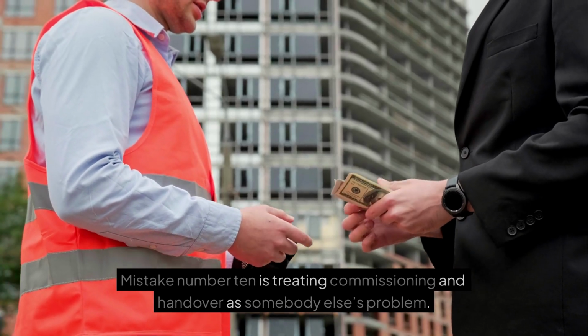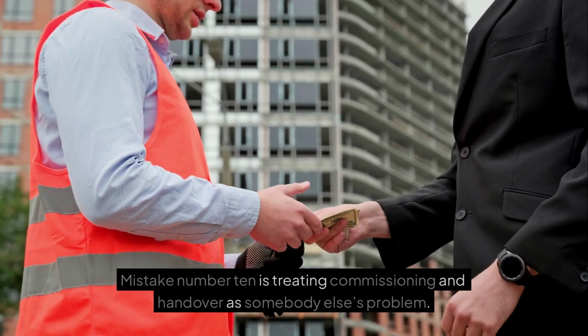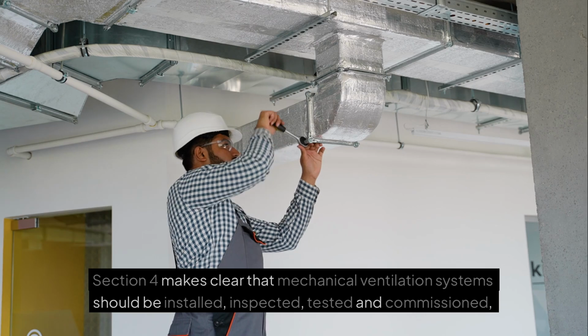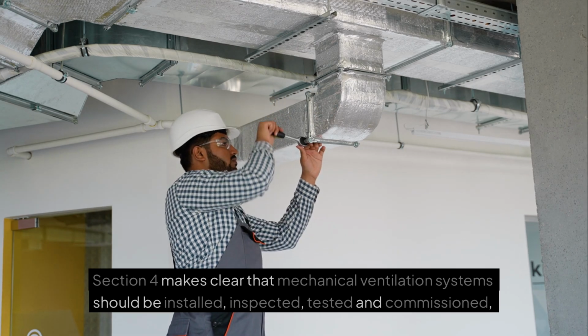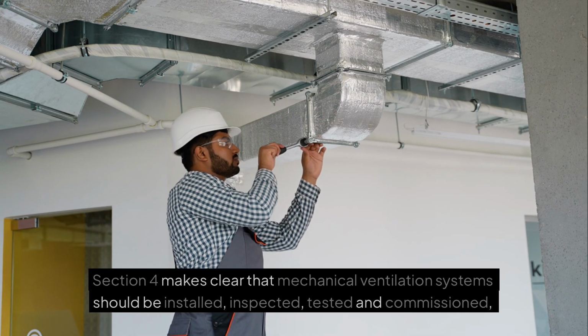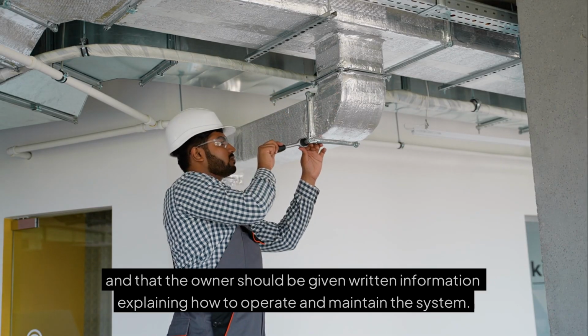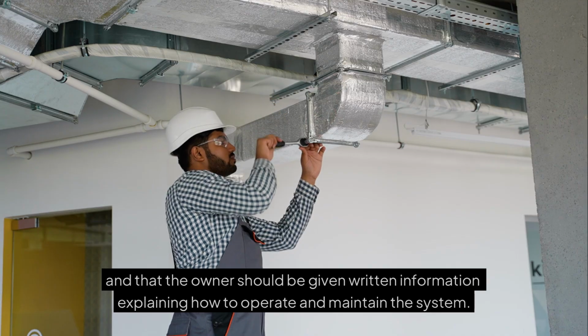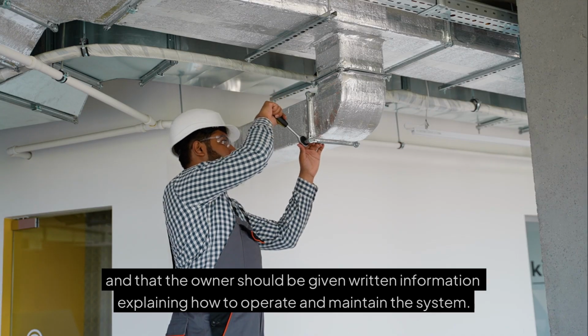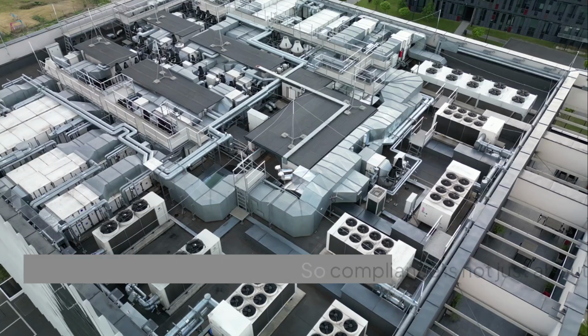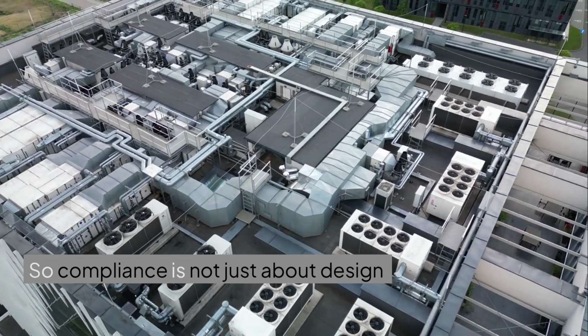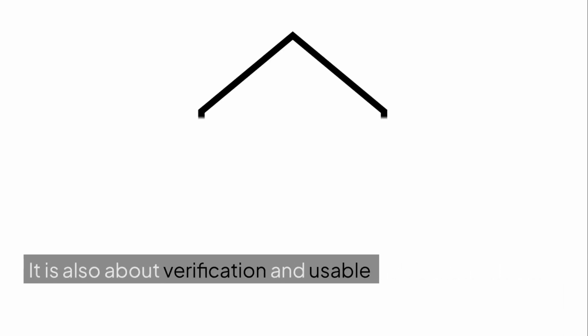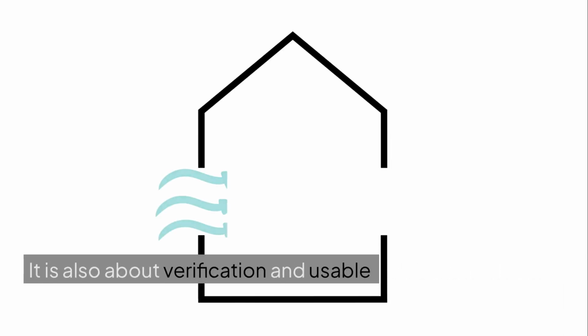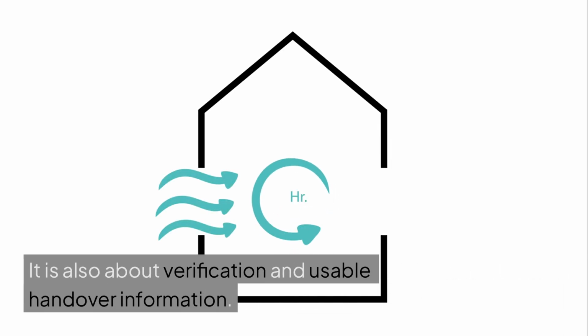Mistake number 10 is treating commissioning and handover as somebody else's problem. Section 4 makes clear that mechanical ventilation systems should be installed, inspected, tested and commissioned, and that the owner should be given written information explaining how to operate and maintain the system. So compliance is not just about design intent. It is also about verification and usable handover information.